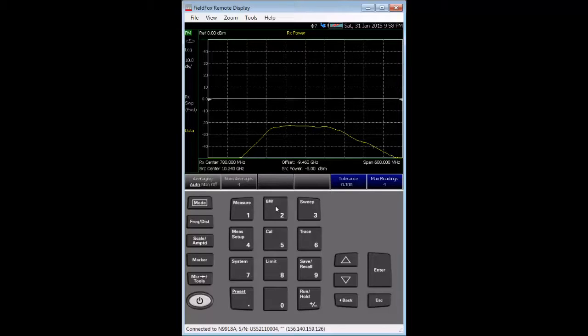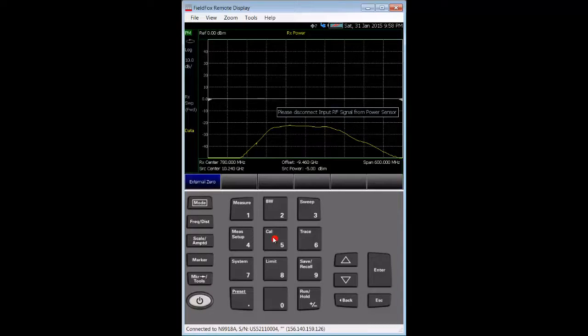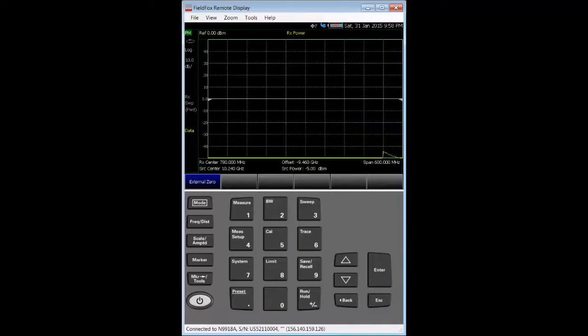For this measurement's calibration, it's important to have the USB power sensor zeroed. So, we press the Cal hard key. Notice the instruction to disconnect the power sensor from any signal source.